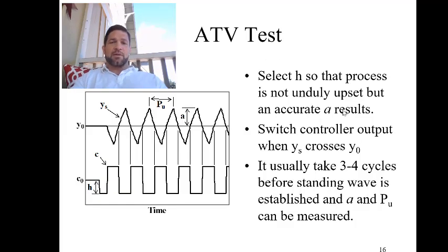So for an ATV test, it's an open loop method so the controller will be turned off and we apply a change in the controller output or we can do a change in the valve position. But generally we step it up and down around the value where it's set and we establish a standing oscillation, and then we use the attributes from the standing oscillation to calculate the PI and possibly D terms for the controller.